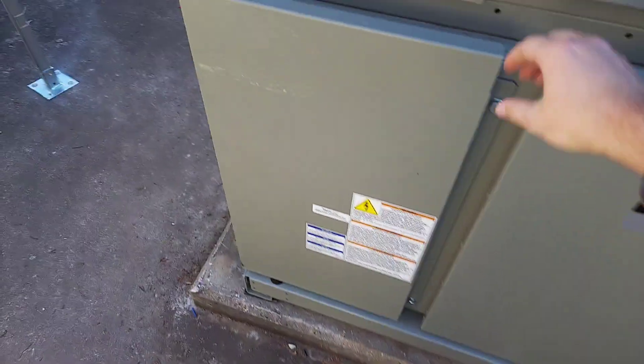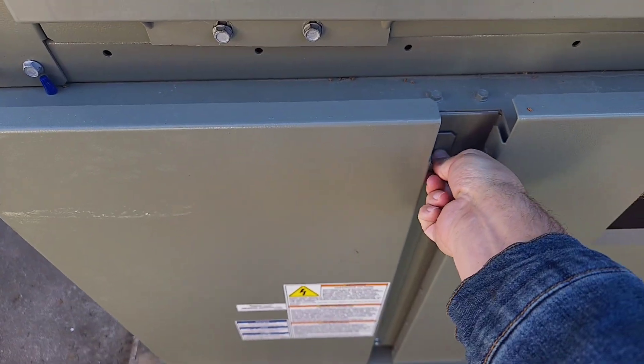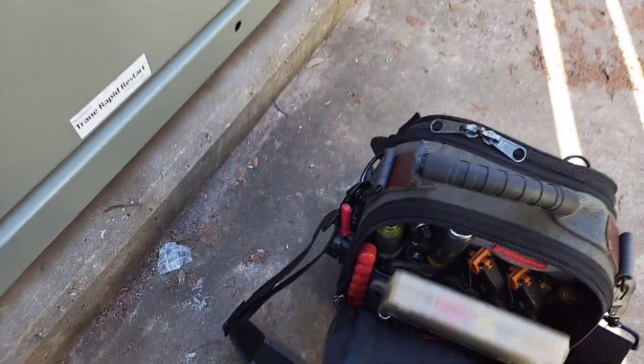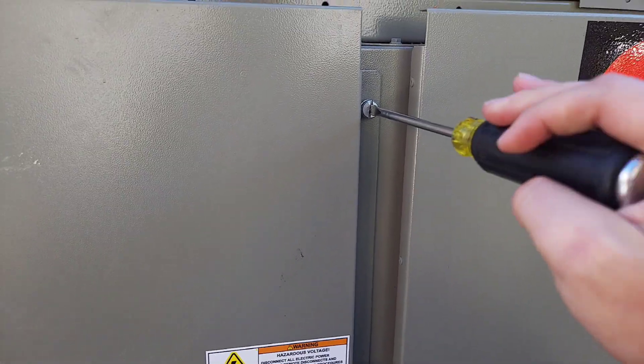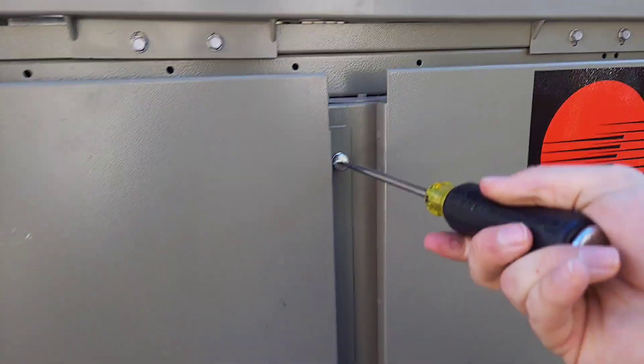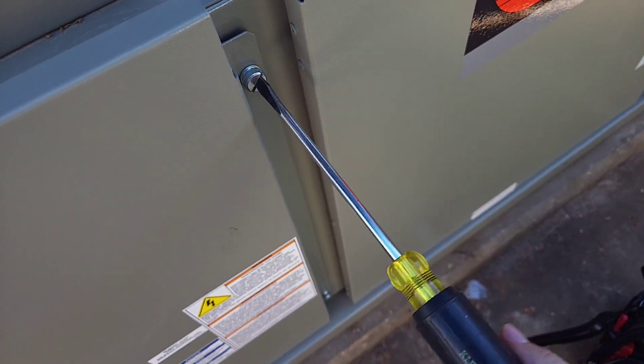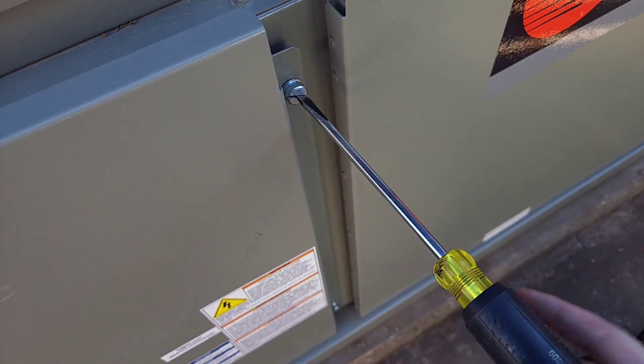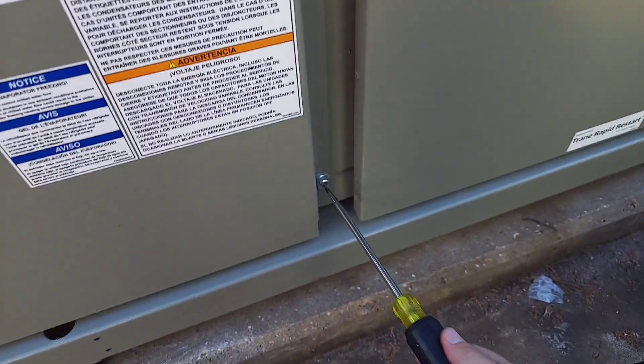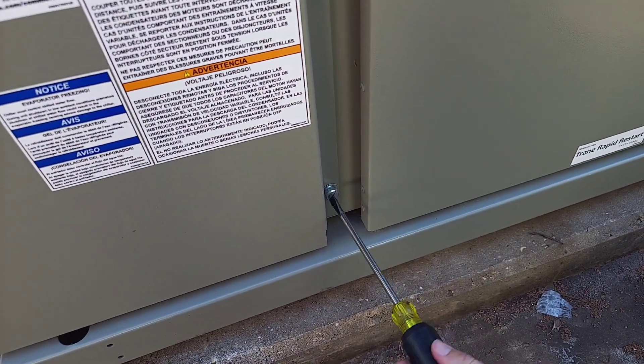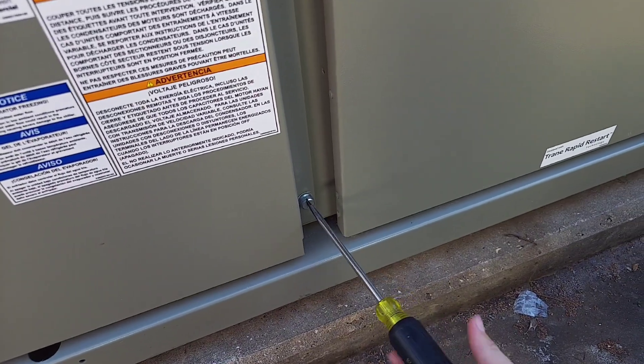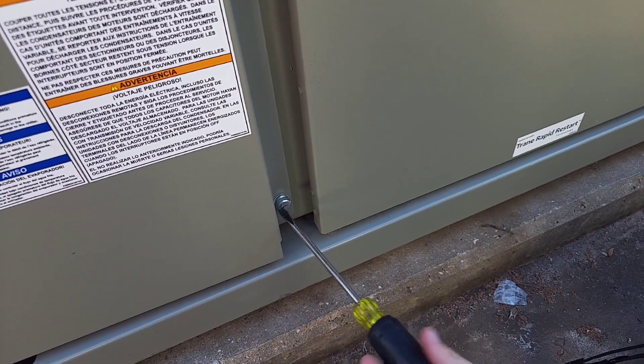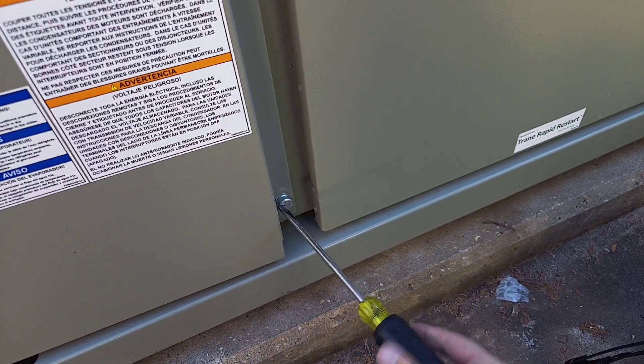Today we're going to be installing a communication card, the BACnet card specifically, on this C-GAM. We just got this thing installed a couple of weeks ago, and we're getting all the fine-tuned things. They didn't originally have it set up when we ordered the chiller for the BACnet card and then decided later to proceed with that so it'll communicate with the automation system. That's what I've got going on today.